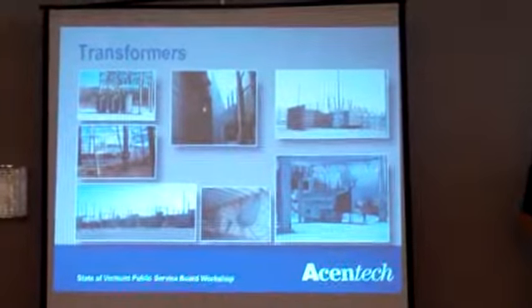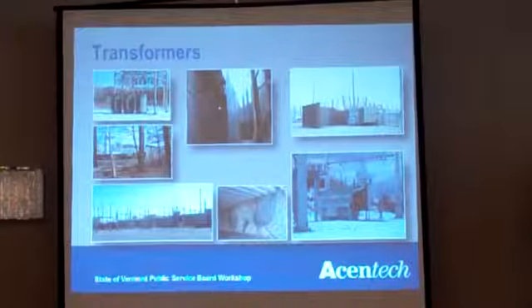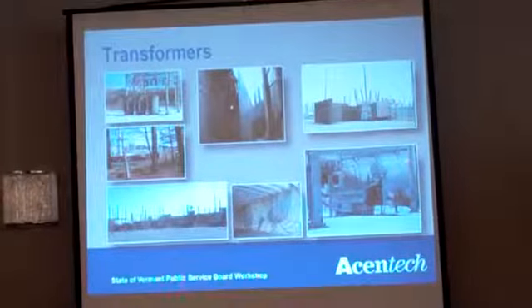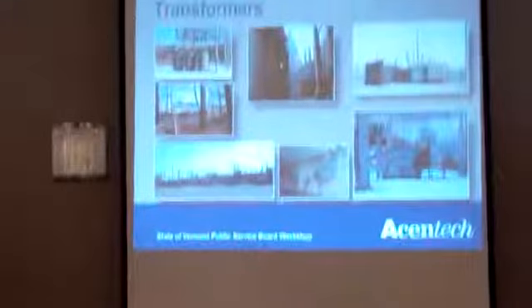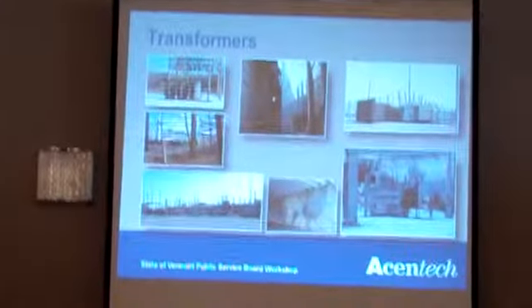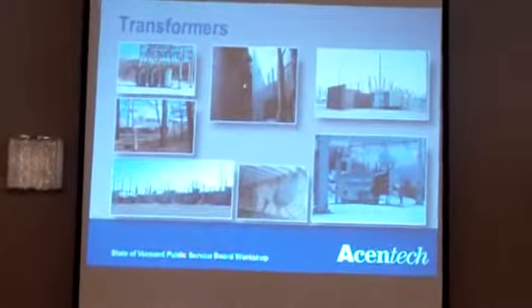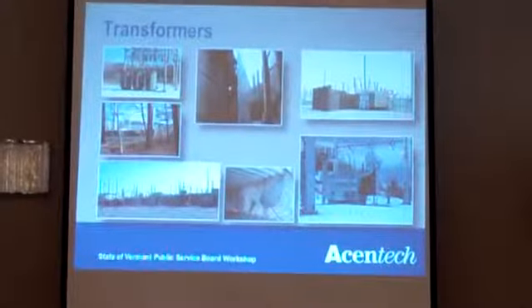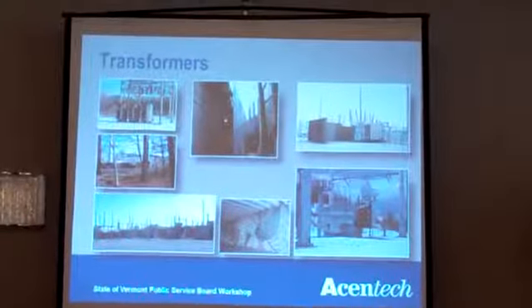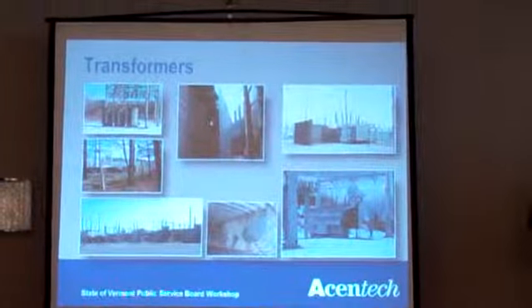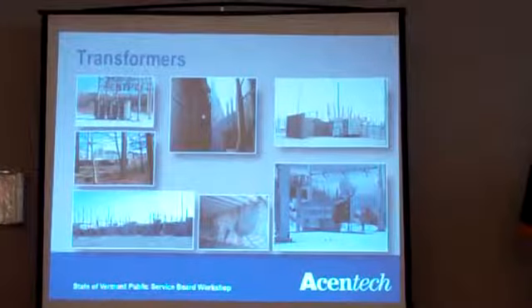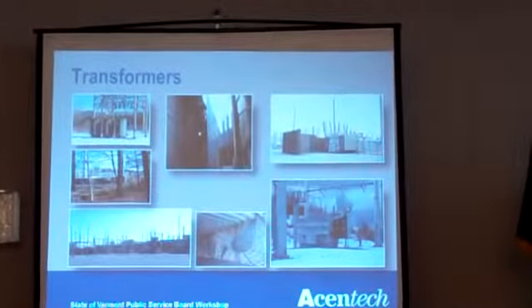Sound is generated by alternating currents within the transformer, causing internal vibration, which is connected both through the oil and structurally out to the casing. The casing then acts as a loudspeaker diaphragm out to the community.